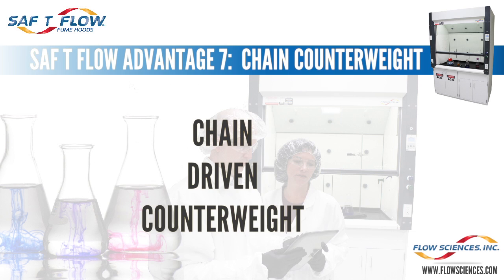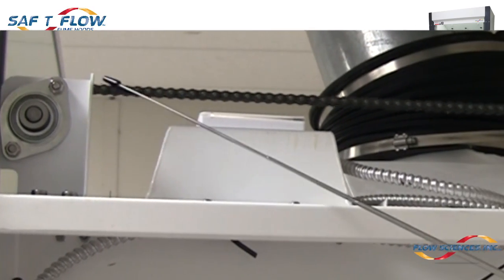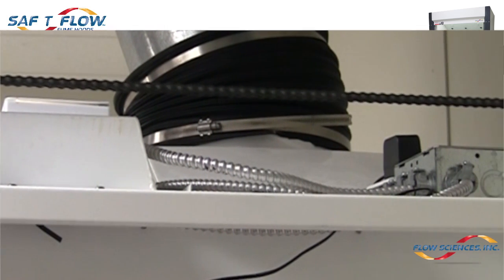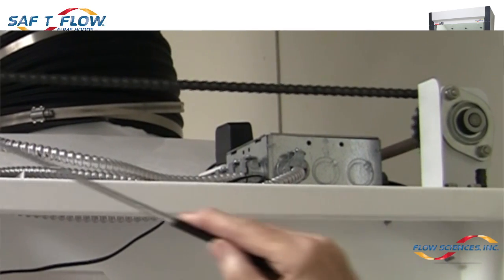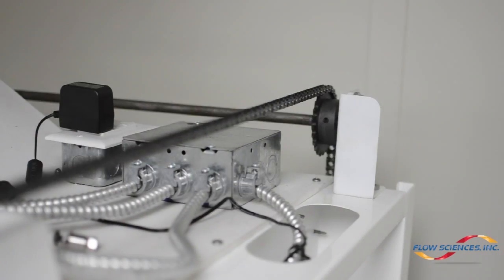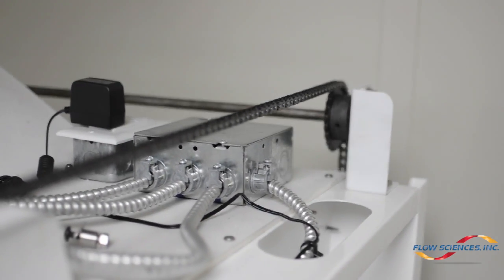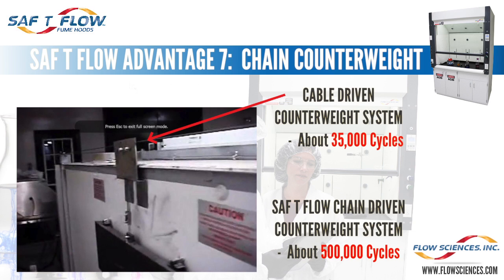Advantage seven: the Saf T Flow chain drive sash counterbalance system eliminates time-consuming and repetitive repairs and adjustments to the old-style cable counterweight system. Our chain drive features two sprocket axles, a heavy-duty set of four sprockets, four bearings — one at each corner of the system — and two number 35 case-hardened steel chains. This chain system will last 500,000 cycles without breaking, compared to the older flimsy cable system on other hoods, which might last only 35,000 cycles before they break or require adjustment.